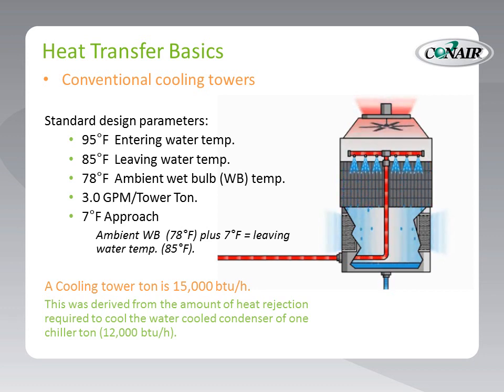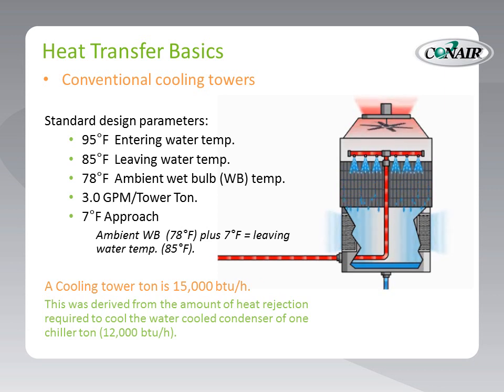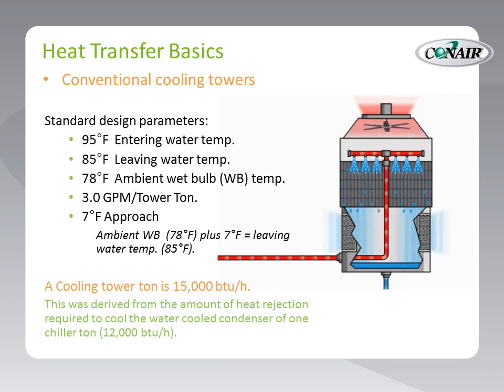For cooling towers, we speak in terms of an approach temperature of 7°F. That means we can provide a leaving water temperature 7 degrees above the ambient wet bulb temperature. We should make a distinction between chiller tons and cooling tower tons. A chiller ton is 12,000 BTUs per hour, derived from the amount of energy required to melt one ton of ice over a 24-hour period. A cooling tower ton is 15,000 BTUs per hour, derived from the average energy required to cool the condenser of a one ton chiller.